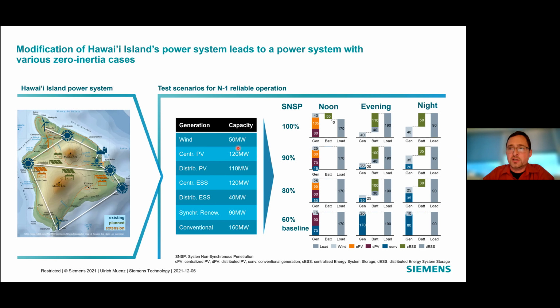The top line, 100%, means there is zero inertia. The second line means 90% SNSP, with one large synchronous machine involved in the system. The third line is two large synchronous machines in the system. The baseline at the bottom is just for comparison; we're not using that for testing, but it's the baseline because that's what the system is today, and where we got study results from HECO.